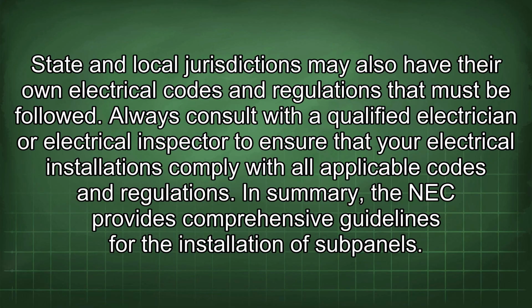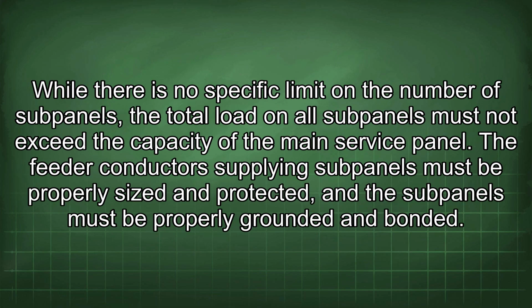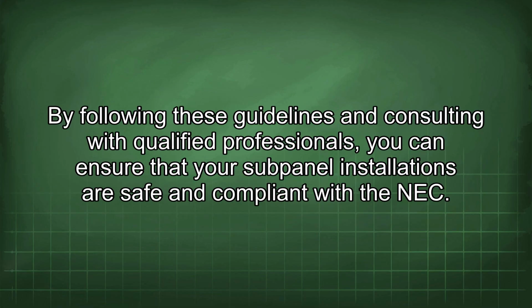In summary, the NEC provides comprehensive guidelines for the installation of subpanels. While there is no specific limit on the number of subpanels, the total load on all subpanels must not exceed the capacity of the main service panel. The feeder conductors supplying subpanels must be properly sized and protected, and the subpanels must be properly grounded and bonded. By following these guidelines and consulting with qualified professionals, you can ensure that your subpanel installations are safe and compliant with the NEC.